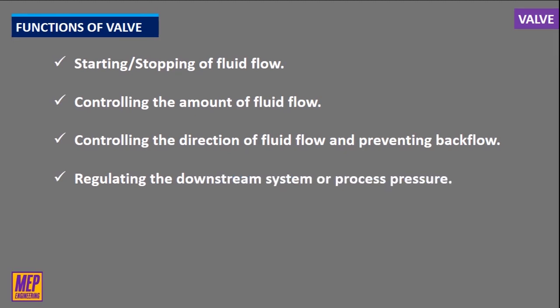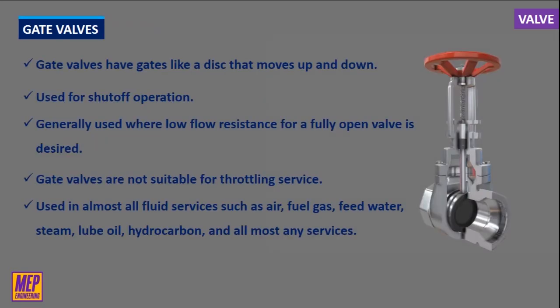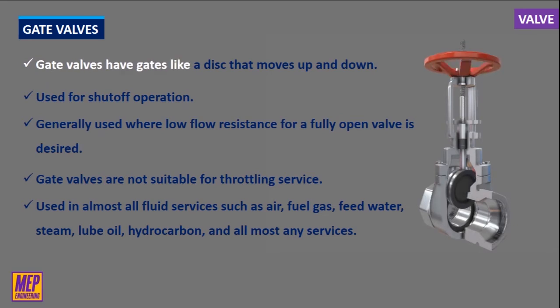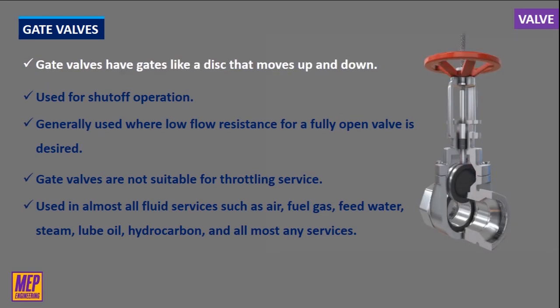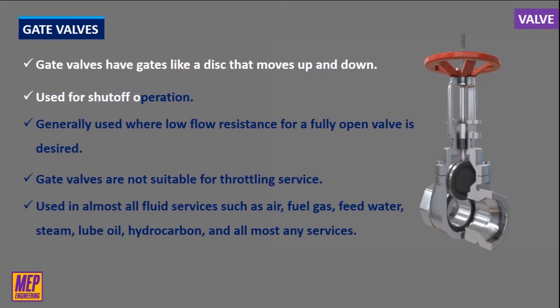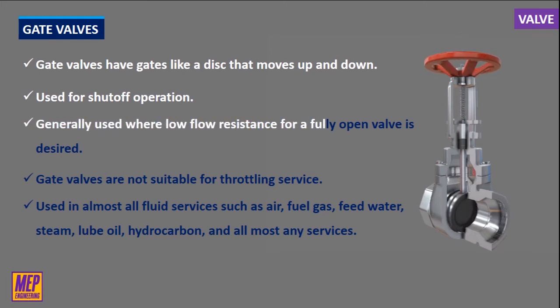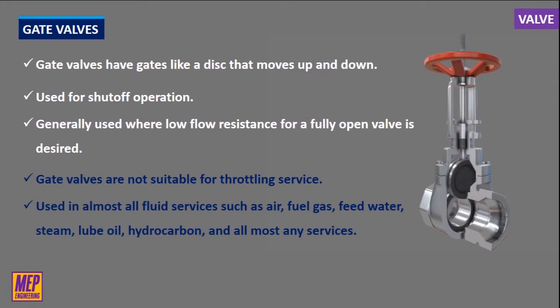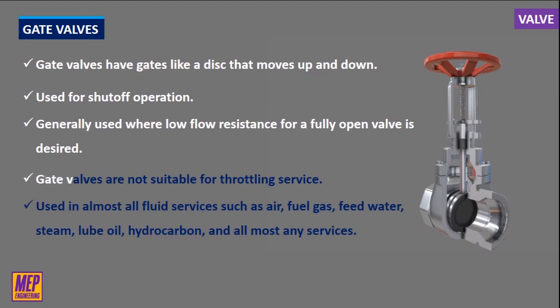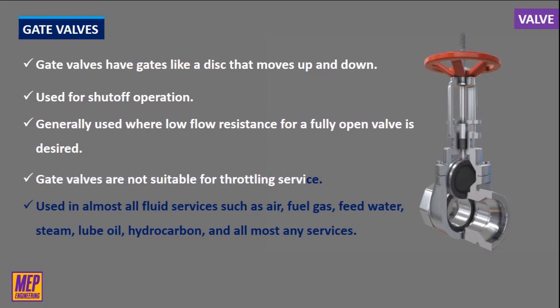Gate valves have gates like a disc that moves up and down with the use of a screwed stem and hand wheel. It is a linear motion valve used for shutoff operation. Gate valves are generally used where low flow resistance for a fully open valve is desired. They are designed to operate either in a fully open or fully closed position. Gate valves are not suitable for throttling service, as extended throttling will damage both the obstructor and seals.